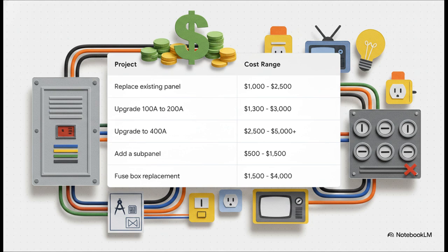Moving all the way up to a 400-amp service is a major project that often starts at $2,500 and can easily exceed $5,000, mostly because it requires heavy utility coordination and brand new incoming conductors. Now, if you just need more circuit slots but you already have enough total power, adding a subpanel is by far your cheapest route, usually between $500 and $1,500.